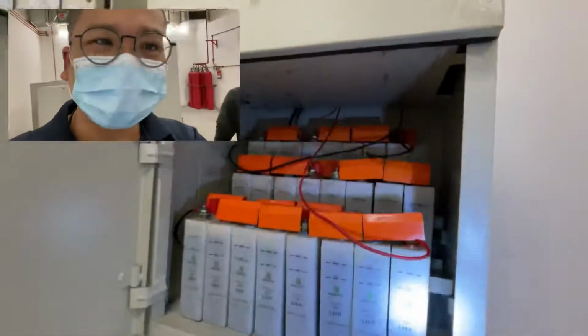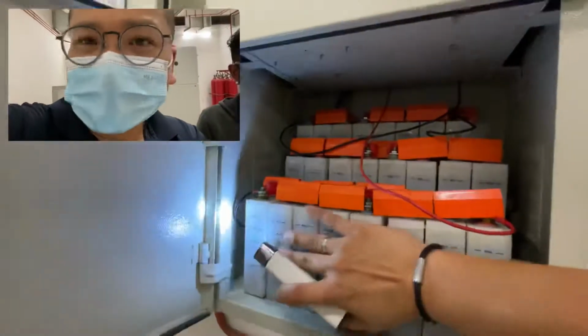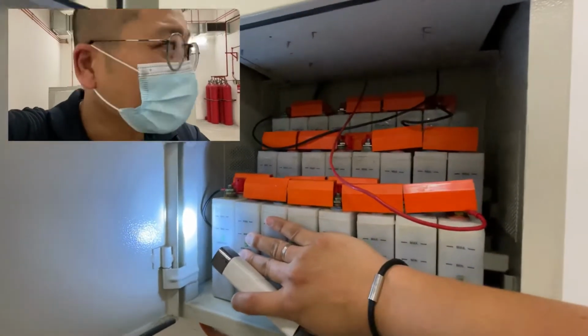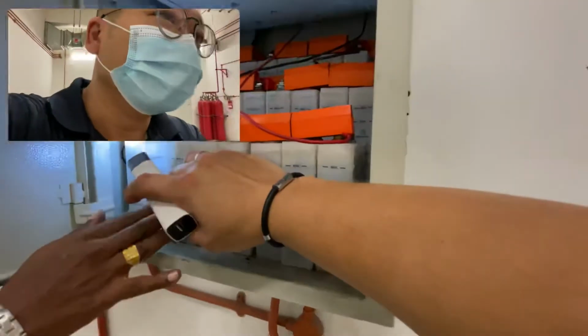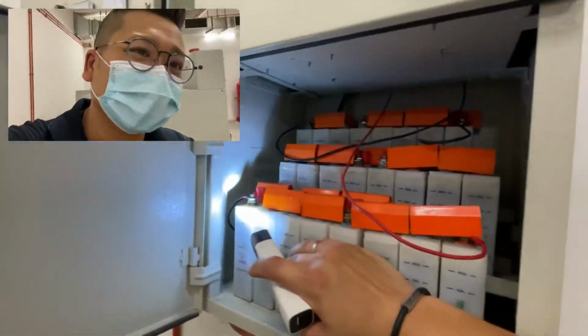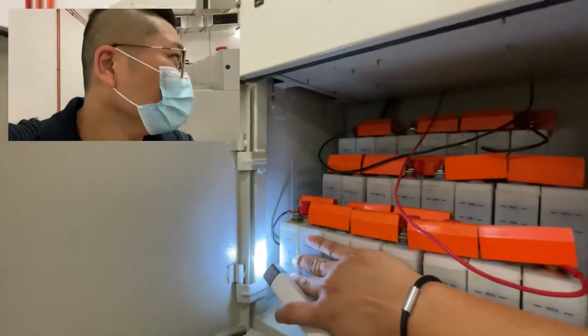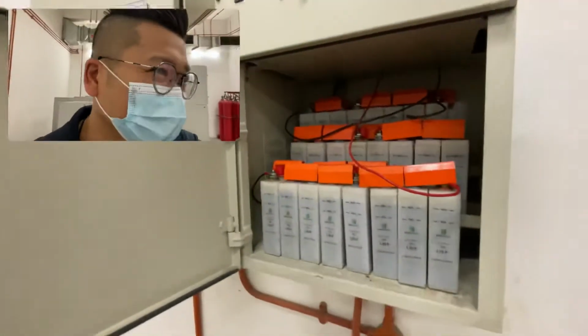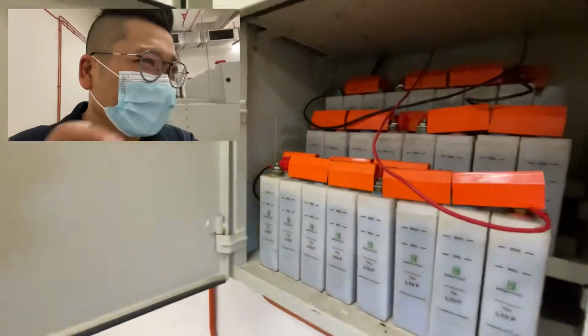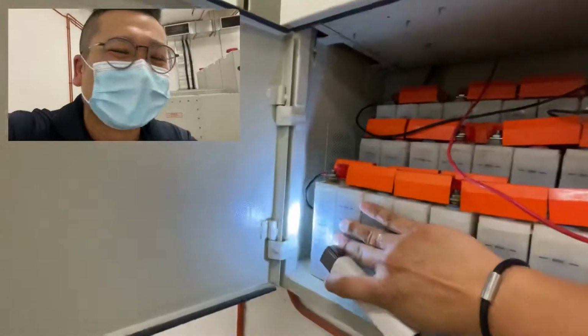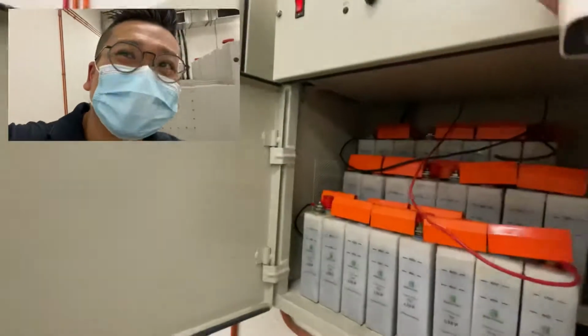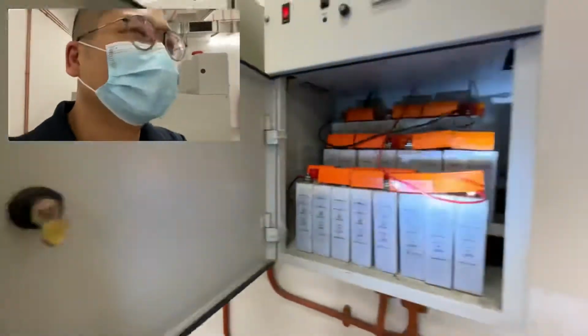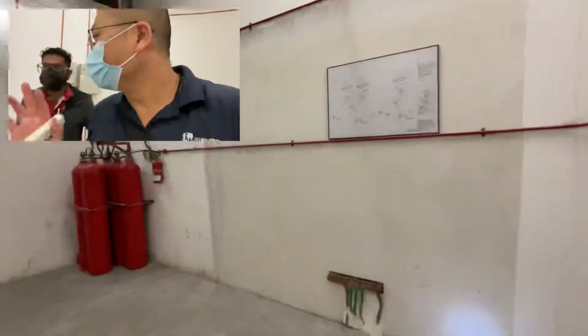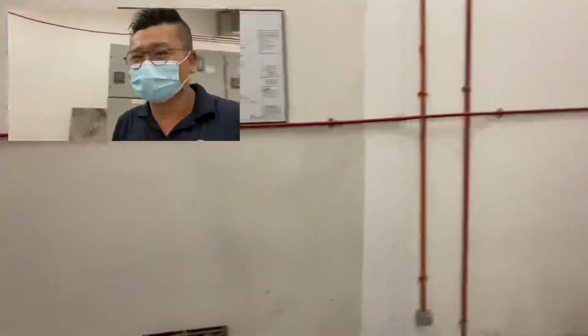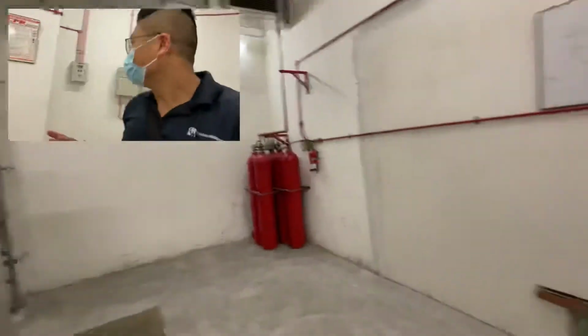How to know the battery is overcharging or not? Put your hand here. If you feel it's warmer than the room temperature, that means overcharge. But like this is okay, same as the room temperature. Some is excessive overcharge, some is slightly overcharged. If it's excessive, you need to fine tune the charger here. But this one is okay. After we check the battery, this room doesn't require any ventilation at this moment because it's not hot. So it's okay if it's not running.